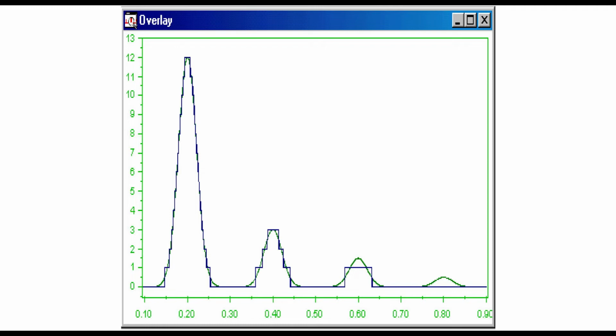This may seem strange, since the effect of this quantization noise is to make the baseline look less noisy. Nevertheless, it does act like noise, in that it causes errors in measurement and small peaks can vanish into the baseline just as they can vanish into the detector noise. This chromatogram is noise-free. If significant amounts of noise are present, then the noise may push the detector signal into adjacent steps and quantified noise will appear.